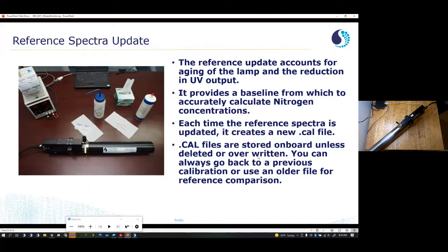Okay, so now we're going to do a reference spectra update. The reason we do this is that it accounts for the aging of the lamp and the reduction in UV output from it. It can also tell you about the health of the sensor, the health of the lamp itself. It provides a baseline from which to accurately calculate nitrate concentrations. It's a little different from a calibration. It just makes sure everything is shifted in the right direction. And it should be done every time before you deploy.